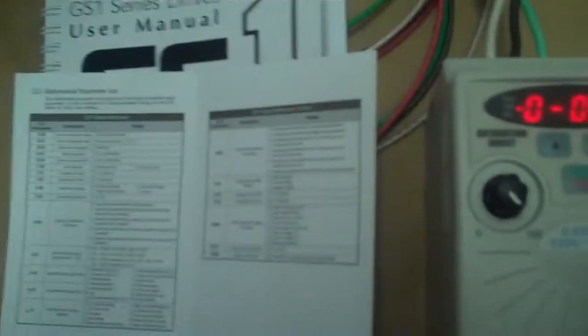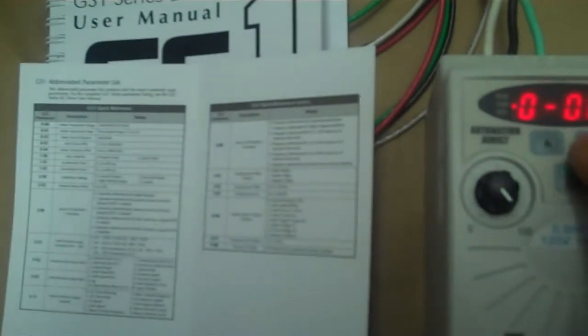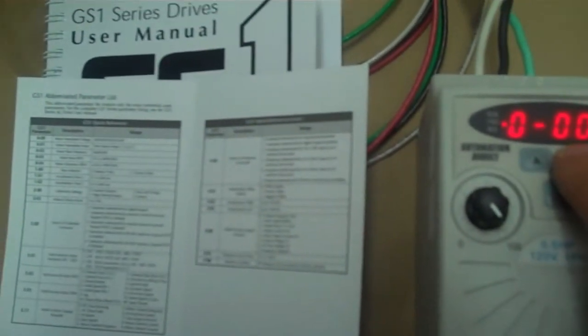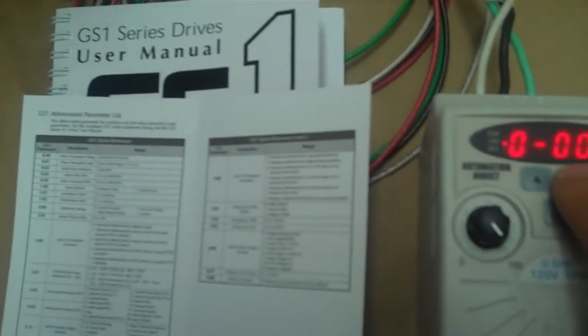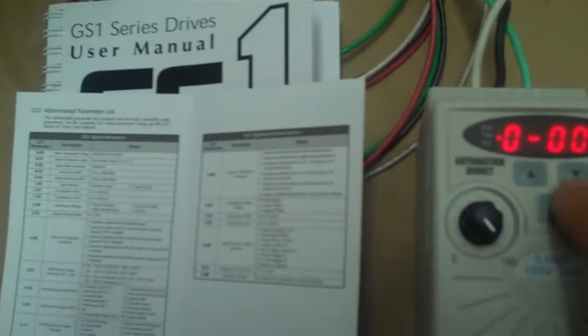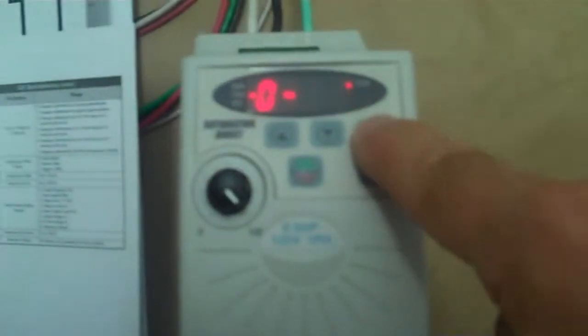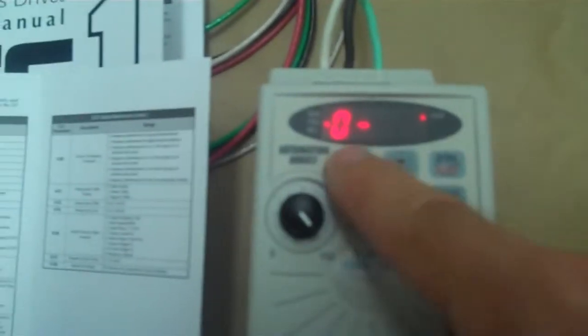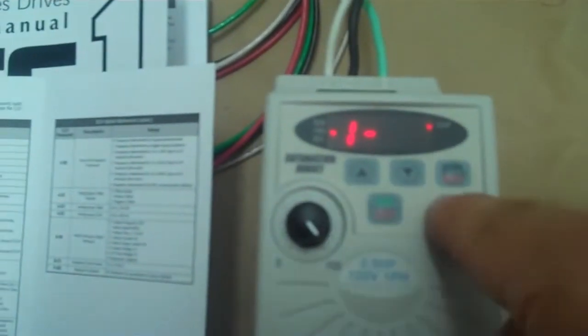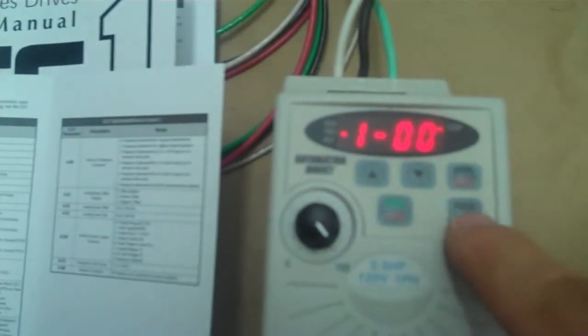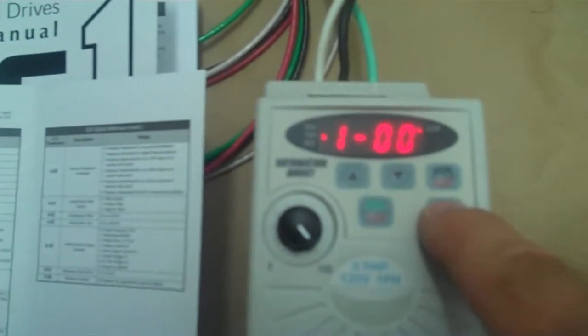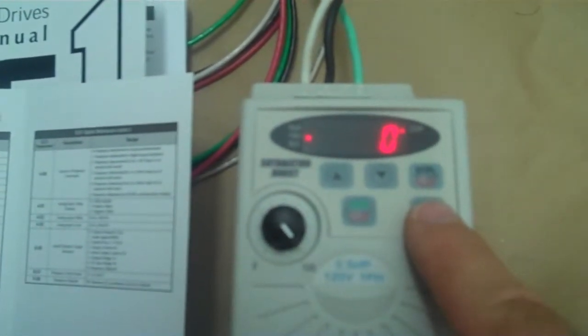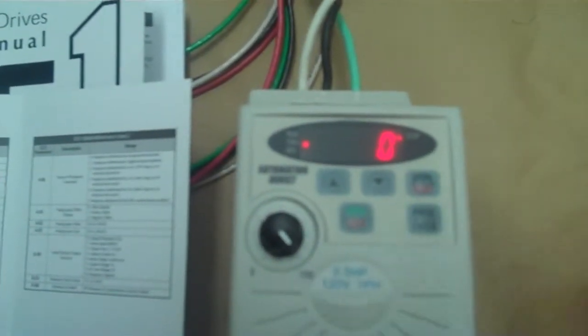We're going to check that one dash zero zero, stop method, is set to ramp to stop rather than coast to stop. So let's get over to one dash zero zero. I'm going to hit the back button which takes us back there, up to one zero zero, and it's set to zero which is ramp to stop, which is what we want, which is cool.